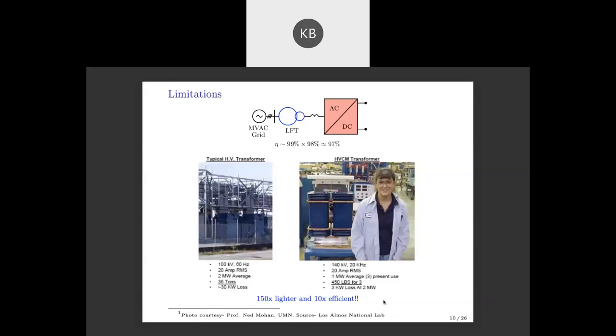Now I will start talking about more advanced stuff, such as the connected system. What we have seen is that here you have your MVAC grid, say 11 kV, three phase, 50 hertz. Then you have a line frequency transformer, a 50 hertz transformer, stepping down the 11 kV to 415 volt, 50 hertz, three phase AC. And then you have your AC to DC converter, or three phase converter, which will make the DC grid for you.